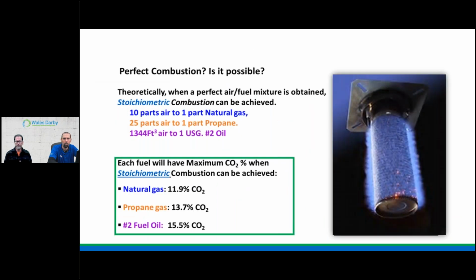All right, perfect combustion. In the world of what we need, air ratio to fuel, stoichiometric is, I think he was a guy, well, I think this is his name, believe it or not. Hey, Stoich. Yeah. So natural gas, 11.9, propane 13.7, you can read this in 15.5 for number 2 fuel oil. The parts per 10 parts air to 1 part gas, and 25 you see there in cubic feet of air to US number 2 oil.